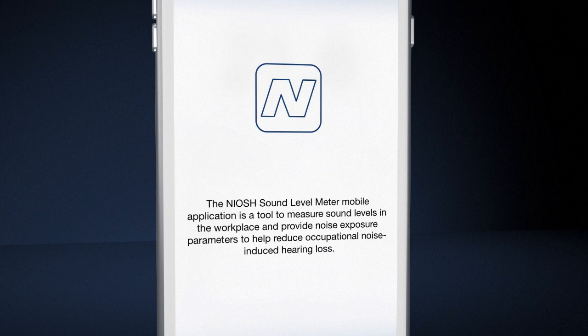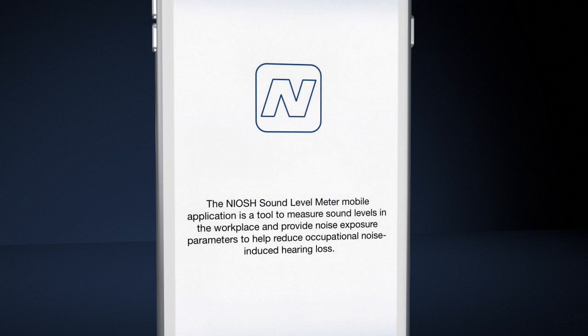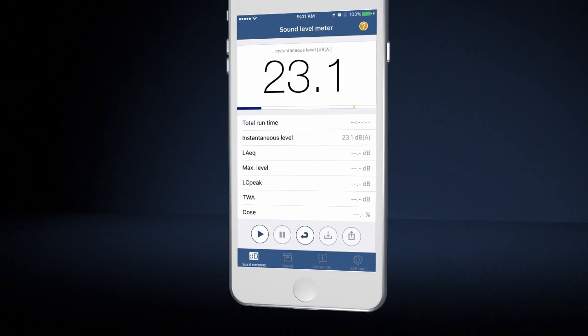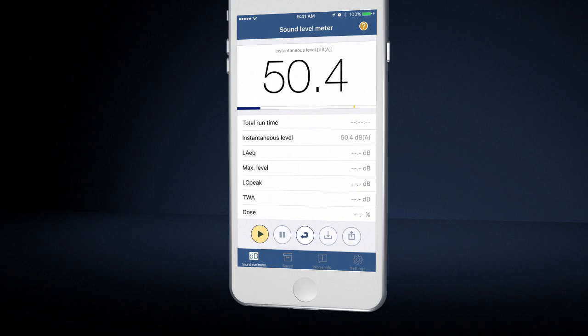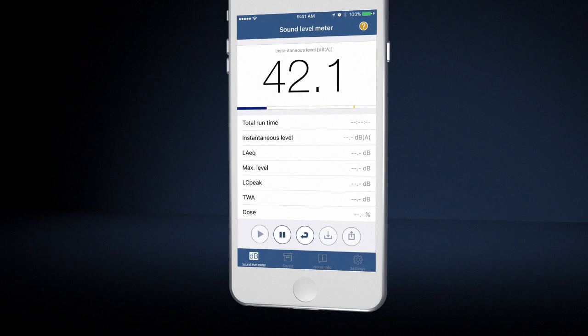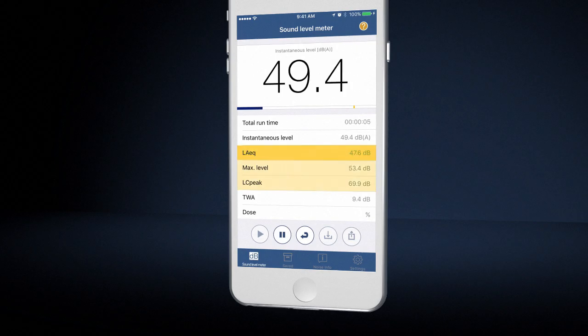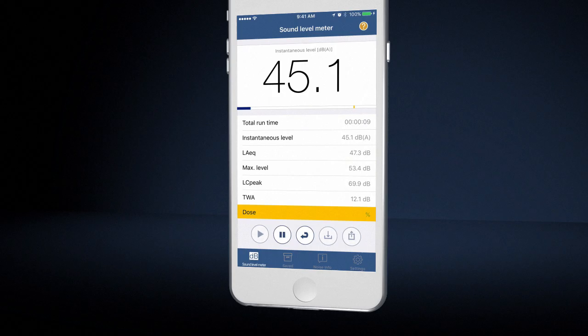The app is preloaded with calibration factors for each model of iOS device. When you launch the app, it immediately displays the instantaneous background sound level. To make a measurement, press the Start Run button and you'll notice that the app will start calculating the different occupational noise exposure metrics such as LAEQ, max and peak levels, time-weighted average, and noise dose.